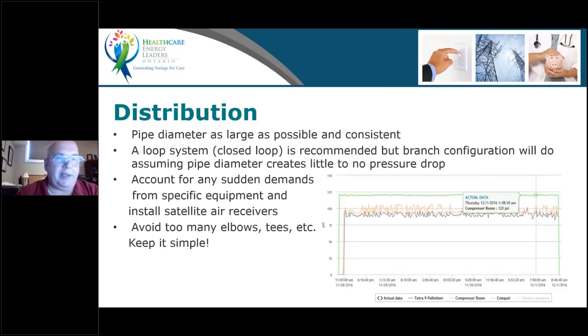Keep the piping diameters as large as possible. A loop system, a closed loop, is much better than a branch. If you've got a branch system, just ensure that the diameter is as large as possible. Satellite tanks at the farthest point or the largest consumer of air when equipment starts up is a good practice. And obviously try to avoid too many elbows, T's, and so on and so forth. Just simply keep it simple.